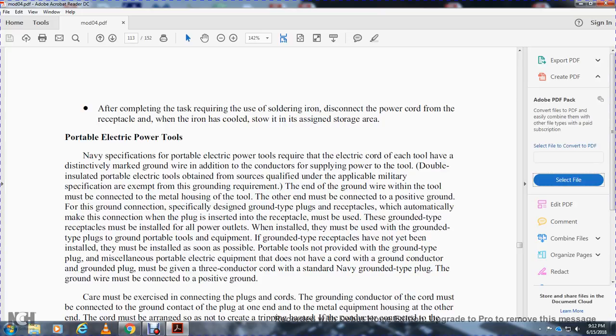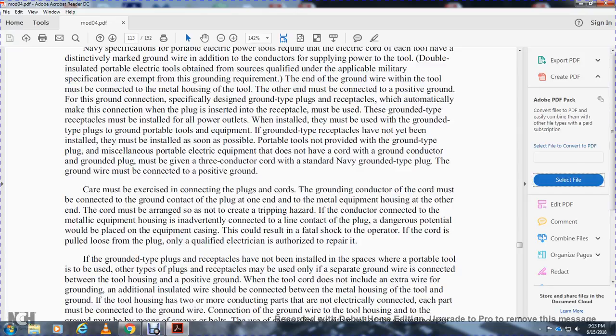Portable electrical power tools: Navy specifications require portable electrical power tools to have an electrical cord with a distinct marker for the ground wire in addition to the conductors supplying power to the tool. Double-insulated power tools obtained from qualified sources are exempt from this grounding requirement. The ground wire within the tool must be connected to the metal housing; the other end is connected to a positive ground through a ground-type plug and receptacle. Ground-type receptacles must be installed at all power outlets — if they have not been installed, they must be installed as soon as possible. Portable tools without a ground-type plug must be given a three-conductor cord with a standard Navy ground-type plug. The ground wire must be connected to a positive ground, and the ground conductor of the cord must be connected to the ground contact of the plug at one end and to the metal equipment housing at the other end. The cord must be arranged so as not to create a tripping hazard.